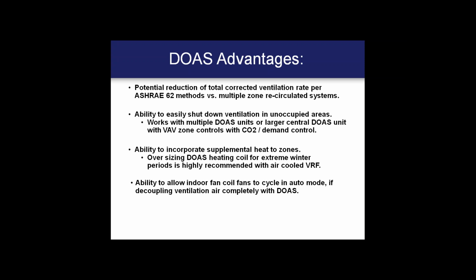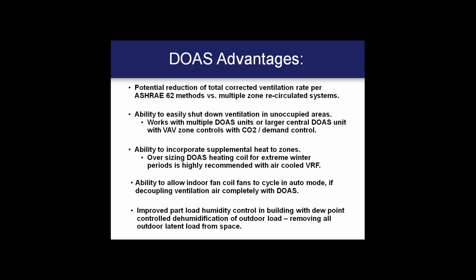And then the ability to allow the indoor unit fans to cycle, I think, is another important advantage if applied correctly. If you're completely decoupling that air from the fan coil itself, the VRF fan coil, then that fan coil can be set up to cycle its fan when thermally satisfied and take advantage of additional fan energy savings. Most of these fans are very low power consumption to begin with, and they do have auto fan modes which step through their speeds, high, medium, and low in response to demand. But in a lot of cases, low speed is still 70% of high. So allowing those units to cycle off if you decouple that fresh air completely can also offer significant savings.